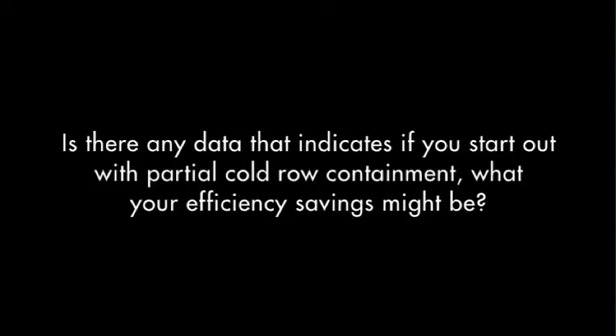The adoption of partial containment: if you look at separating your hot and cold air streams with partial or total containment, think about partial as helping you improve your capability to cool equipment in all spaces of your IT equipment, meaning the performance of the existing data center. And then think about total containment as having the ability to not only predictably, reliably cool all your IT equipment, but also have the opportunity to take advantage of some of the efficiency gains. So with partial containment, I wouldn't necessarily say you're going to have a big windfall in efficiency gains. I would say you're going to have a bigger windfall in more usable IT space that you historically were afraid to use because of hotspots.